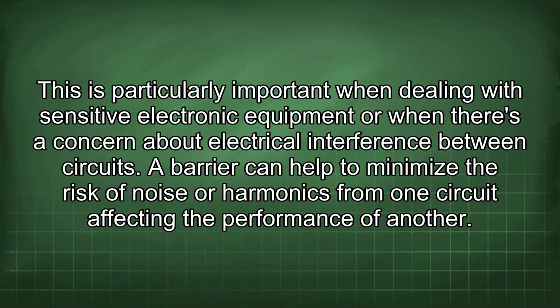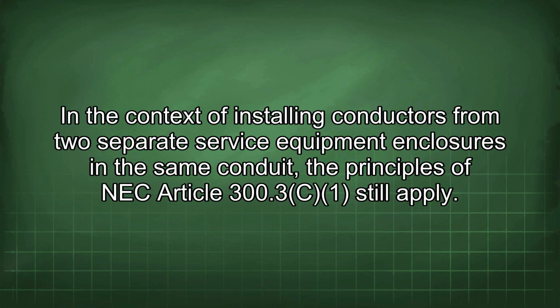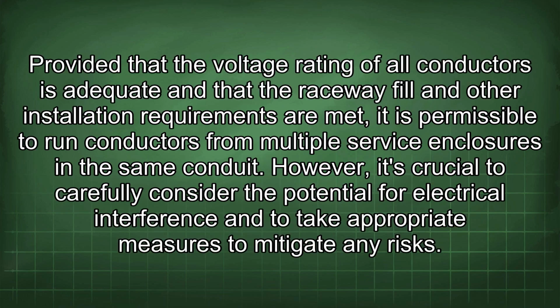of another. In the context of installing conductors from two separate service equipment enclosures in the same conduit, the principles of NEC Article 300.3(C)(1) still apply. Provided that the voltage rating of all conductors is adequate and that the raceway fill and other installation requirements are met, it is permissible to run conductors from multiple service enclosures in the same conduit. However, it's crucial to carefully consider the potential for electrical interference and to take appropriate measures to mitigate any risks.